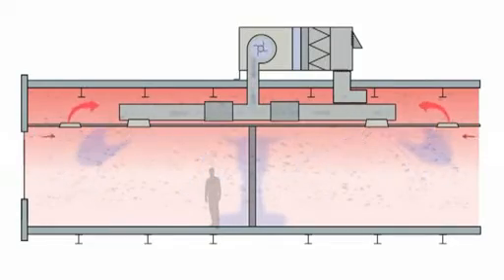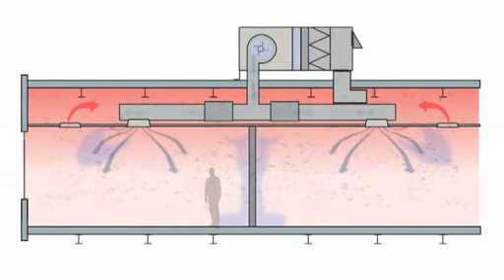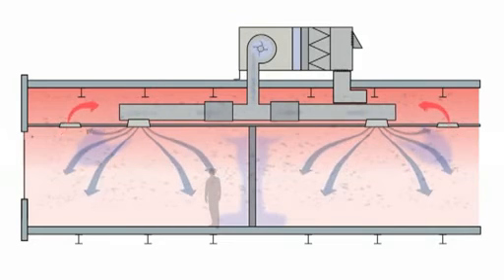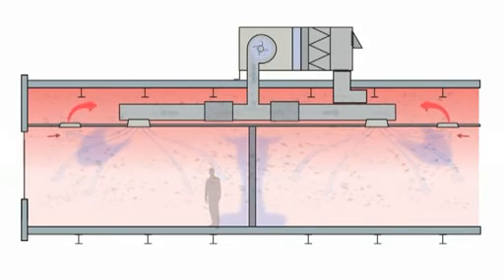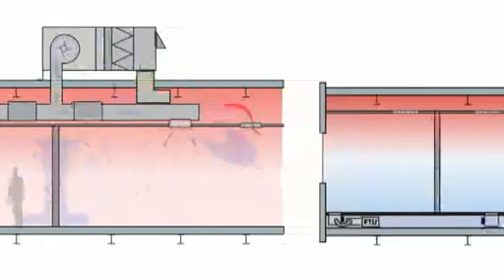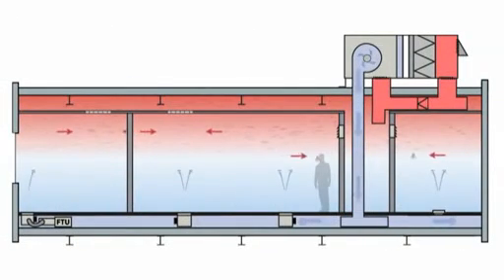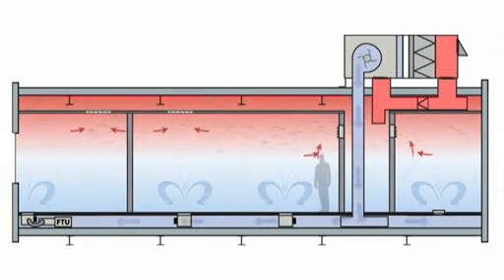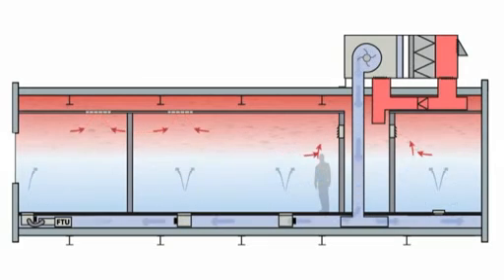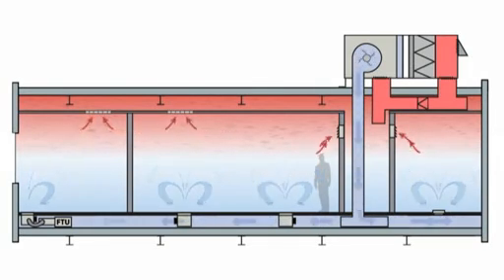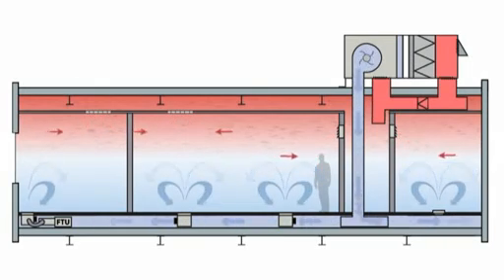Ducted overhead mixing systems, diffusers, and return grills are generally located high in the space, which may to some extent short-circuit some of the conditioned air back into the return, reducing the cooling and mixing effect. With underfloor air, it delivers all the air low in the space and returns it all high. The air enters the space and is mixed in about the first four to seven feet, allowing most of the heat and contaminants to stratify into the unoccupied zone where return air is drawn from.